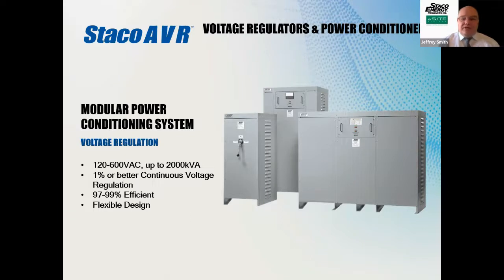The modular power conditioning systems. This is what the AVR type systems would look like. 120 volts to 600 volts, up to 2000 kVA. We've got a 1% or better continuous voltage regulation, 97 to 99% efficient, variable flexible design. We do a lot of these systems, but this is, I guess, what I would call the slower system. It could take up to 2 to 3 cycles to get your voltages back up to the level that you're looking for.